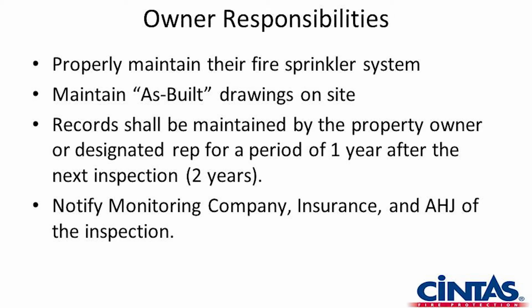Records shall be maintained by the property owner or designated representative for a period of 1 year after the next inspection. So basically, they're saying that a record has to be kept for 2 years. All of our inspections we hold for the life of our customer. We have some customers that came in the door when I walked in the door, and we still refer back to those inspection reports sometimes when we're trying to figure out a problem that's going on with the building.